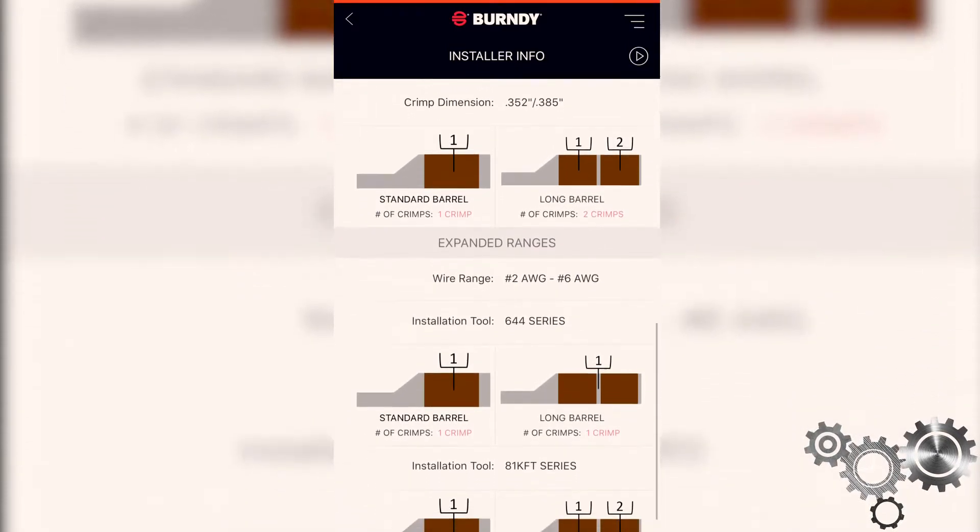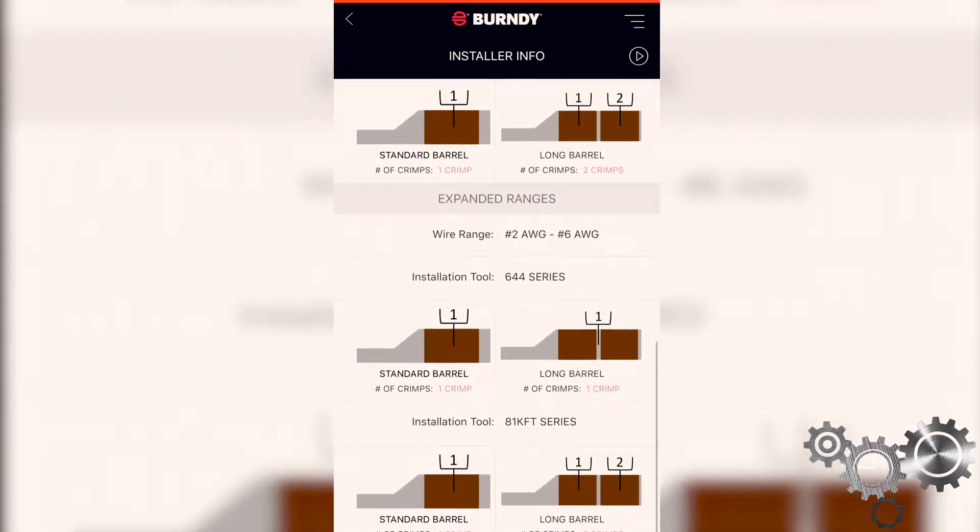It'll also show two illustrations — a standard barrel lug and a long barrel lug. It'll identify the number of crimps for each with that die and tool selection. It'll indicate the approximate location of each of those crimps and show the crimp direction with an indicator of number one and number two and so on sequentially.